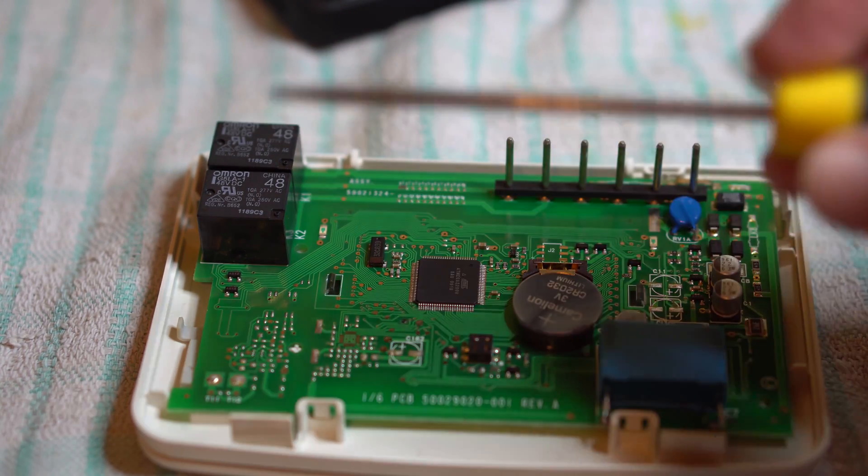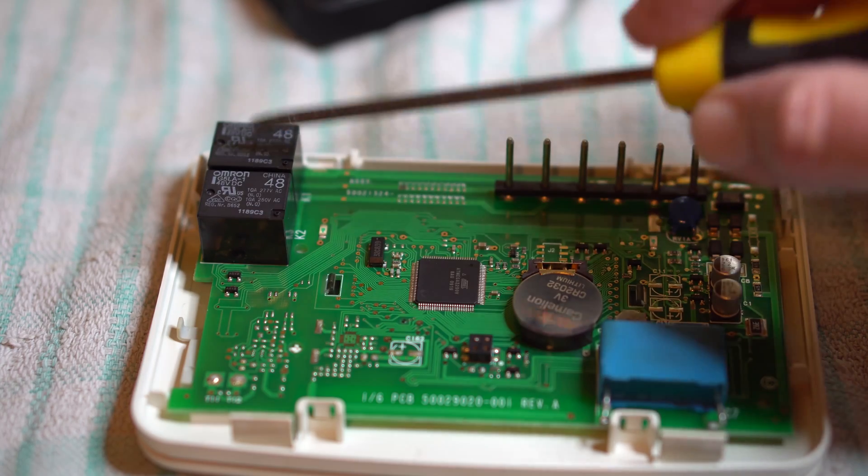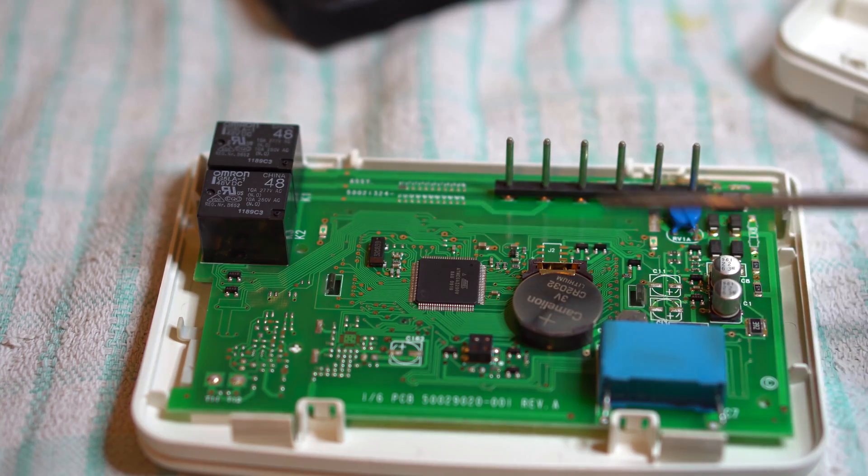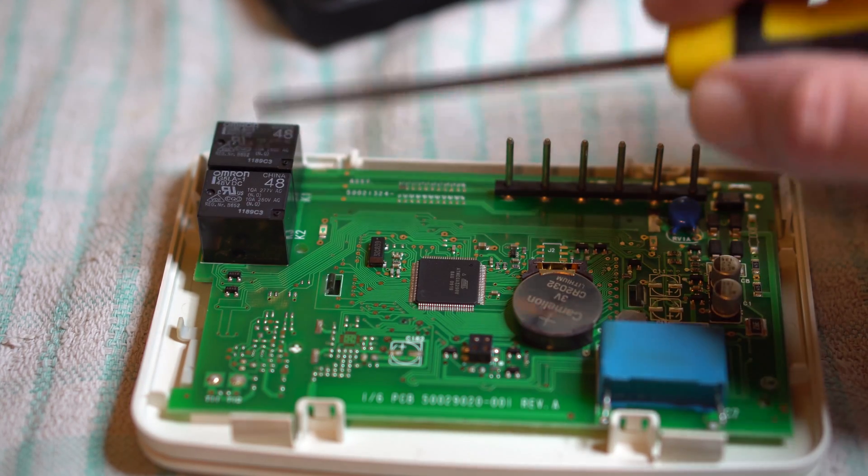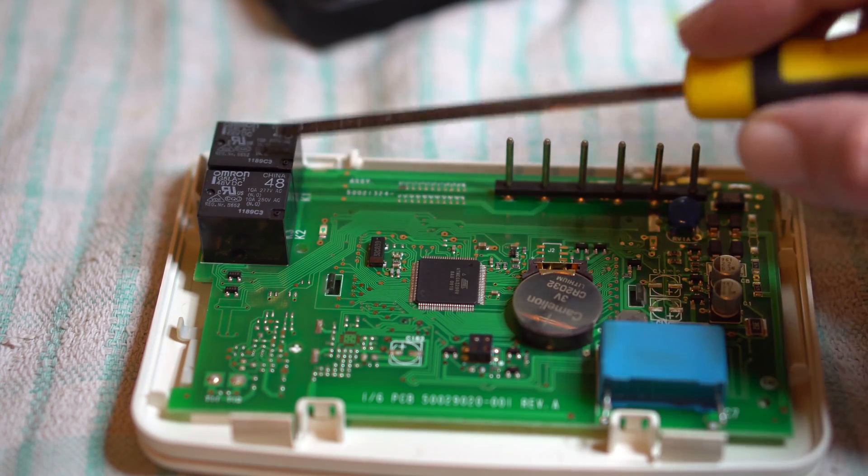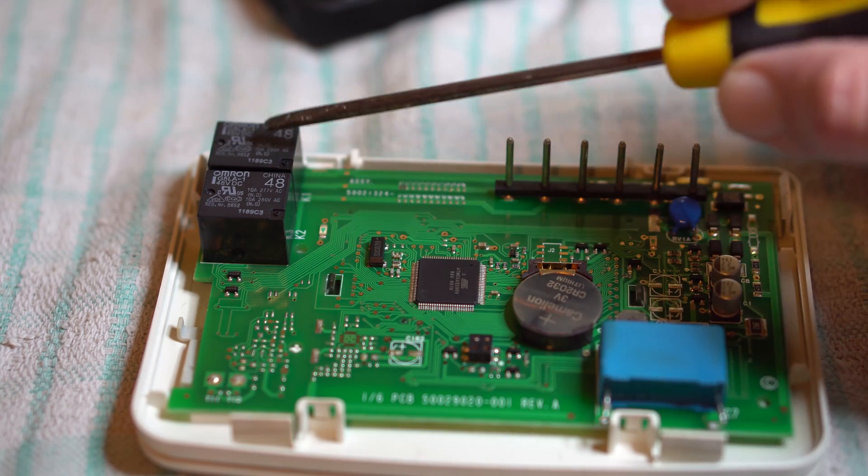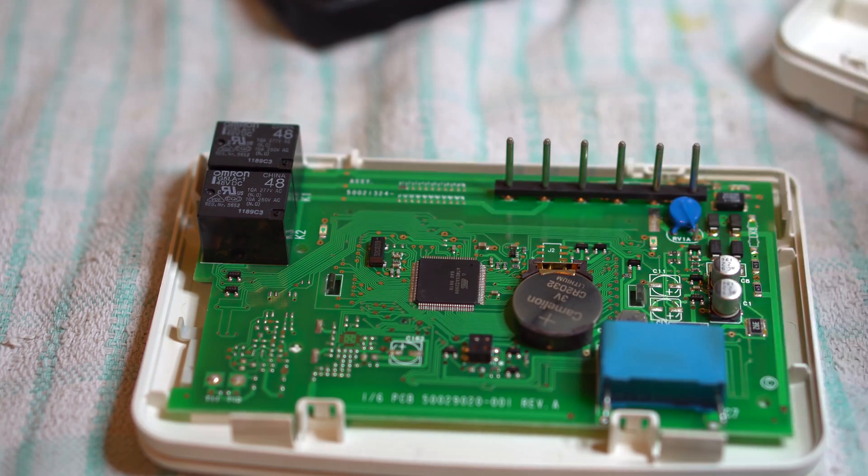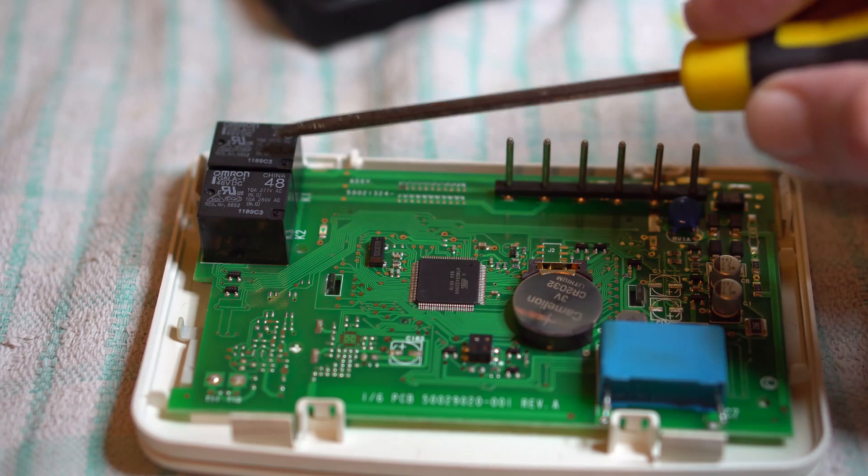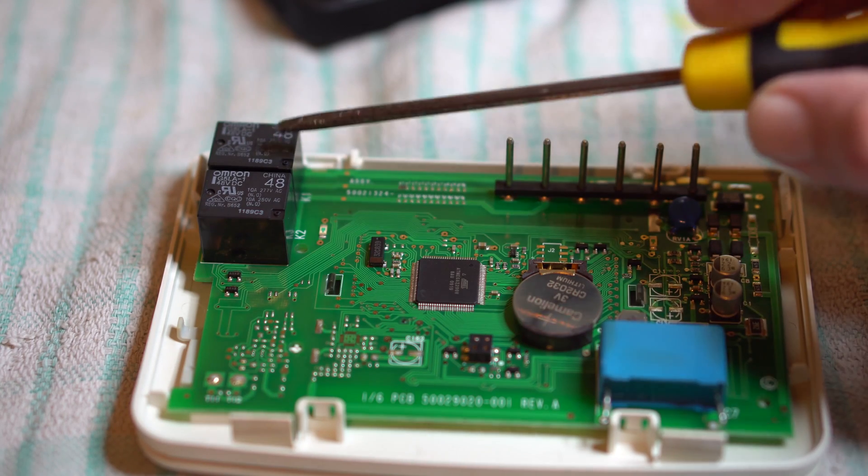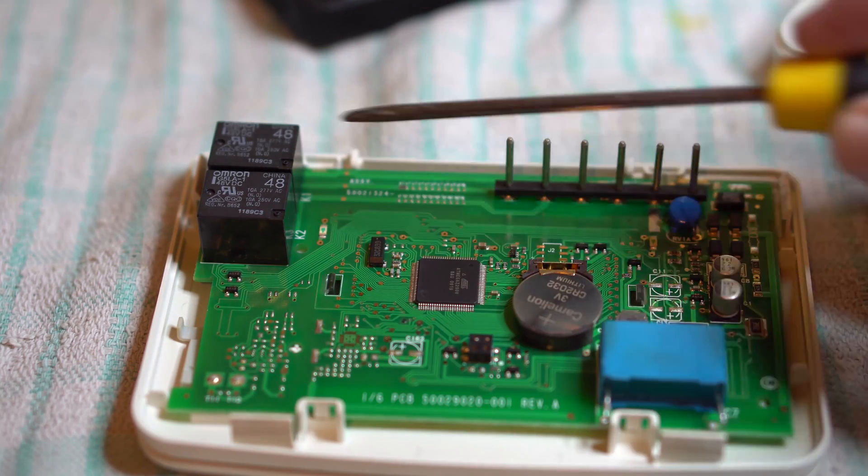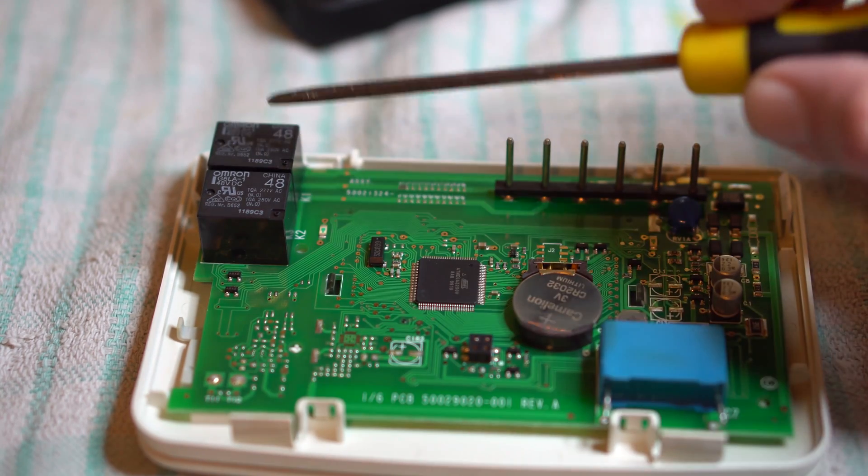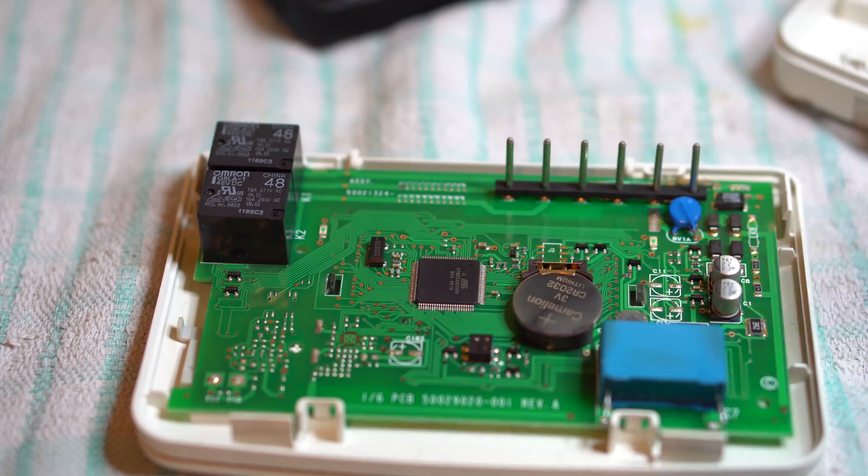Whilst the hot water was on, if you turn the central heating on, there was sometimes enough power to bring in this second relay, but last night, it was zero degrees outside, we're in January 2017, there wasn't sufficient power to pull the second relay in, so the central heating pump wasn't coming in.